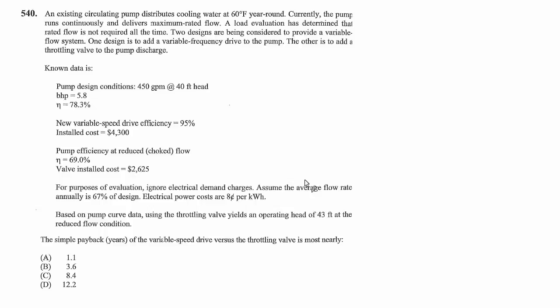Pump efficiency at reduced choked flow efficiency is 69%, and the valve installed cost is $2,625. For purposes of evaluation, ignore electrical demand charges. Assume the average flow rate annually is 67% of design. Electrical power costs are $0.08 per kilowatt hour. Based on pump curve data, using the throttling valve yields an operating head of 43 feet at the reduced flow condition. The simple payback in years of the variable speed drive versus the throttling valve is most nearly what?